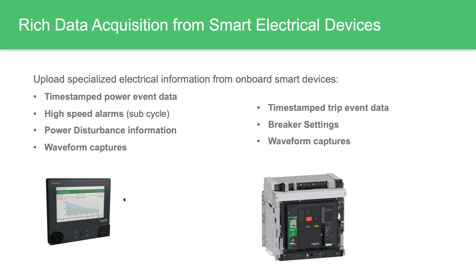Another thing to consider that's often overlooked is the built-in data model for power and energy. This is really a predefined data model that has measurement names tied to the attribute. It enables consistent mapping of data names and parameters across different devices and different models of metering devices, so the software in the power management systems knows exactly how to handle that specific data regardless of the device it's coming from.